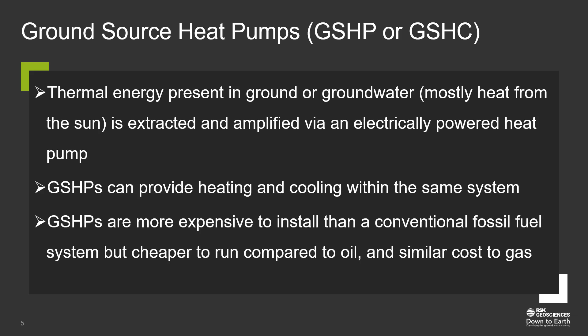Here's a diagram illustrating how they work. It's similar technology to a domestic refrigerator. If you put your hand on the back of a fridge, it might feel warm, because the pump extracts heat from the air and isolates it. In a ground source heat pump, we take that extracted heat and use it to heat hot water. It needs a bit of power to run, mainly electricity, and the efficiency of the heat pump is called its coefficient of performance, or COP - the ratio between the heating achieved and the power taken to run it.